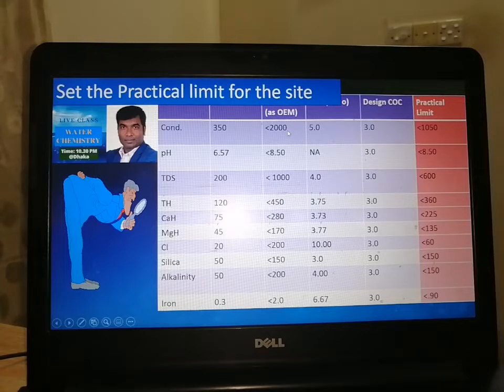So what level should I maintain for my system, as silica is my critical ion? I can't do anything for silica in the raw water. Especially for a cooling system or a simple system, it is difficult to reduce silica, because we use either a softener or other treatment that does not reduce silica. So we have to set our parameters. If I consider a cycle of concentration of 3, I have to multiply the makeup water parameter by 3 and set the limit for the particular system.